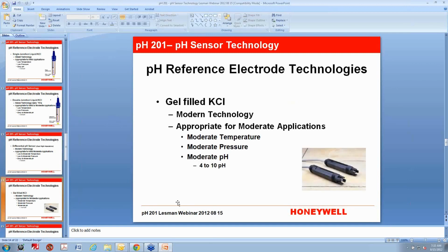Okay, the next one up is the gel-filled potassium chloride reference, and that is probably what I see out there more than anything else out in processes. It was a huge step forward. Between the liquid fill and the gel fill, the industry went through what's called a slurry-filled reference electrode fill. That slurry was an attempt to make the fluid thicker so that process fluid couldn't get in, less compressible, harder to mix, etc. So it was a real boon when manufacturers came out with this gel technology.